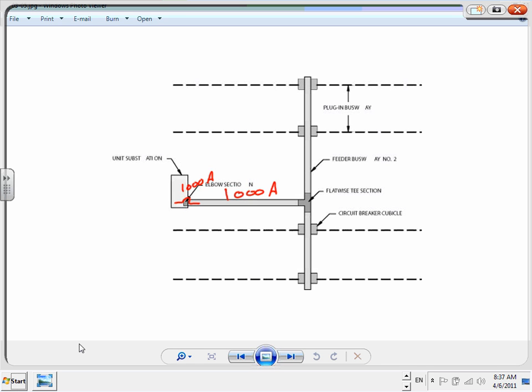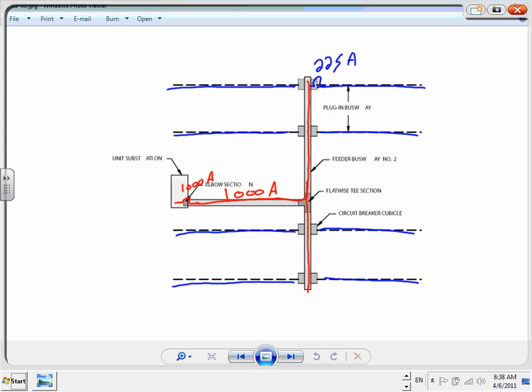And then you're going to go to plug-in busways. I'm going to highlight the plug-in busways in here, and this is typically what you guys are going to be doing. This is my feeder busway coming in. I want to remind you that you need to size an overcurrent protection device, which will be 225 amp. The smallest plug-in busway that you can get is 225. It's not worth putting anything less than 225.